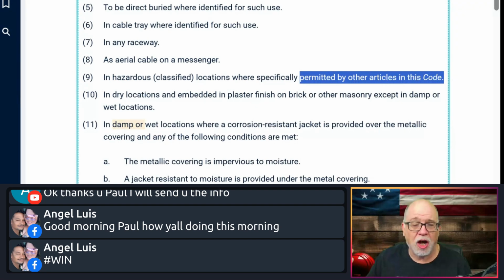And of course, you have other locations like commercial garages, both minor and major, that may give the allowance of use of MC cable. The deal with that is you have to watch and see, because in those hazard classified locations, it may call for a specific type of MC. It might call for HLMC or something that denotes it's been evaluated for use in a hazardous location. But at the end of the day, those specific articles, like it says here, other articles in the code will have certain sections that may permit the use of MC cable, but it may be restricted to certain types.